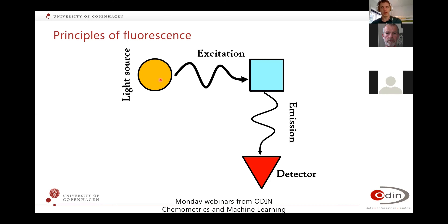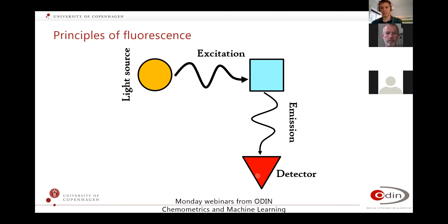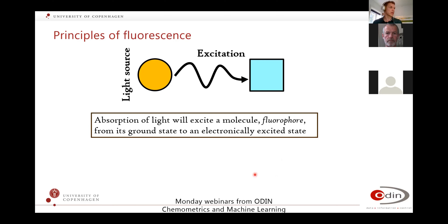In fluorescence we have a light source — typically a xenon lamp — that goes in and hits the sample. If you have fluorophores there, they will be excited. If you have absorbers, they will absorb some of the light. Things will be excited, and then if you have fluorophores, they will also emit some light that we can detect and record on a detector. Absorption will happen for many different molecules, but only the fluorophores are the ones we can spot by fluorescence.